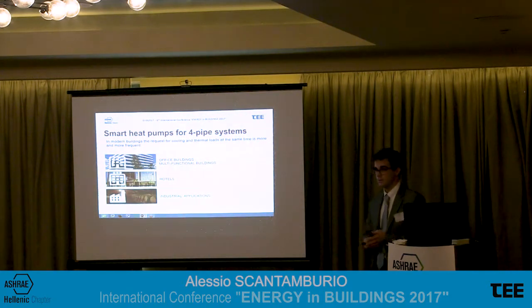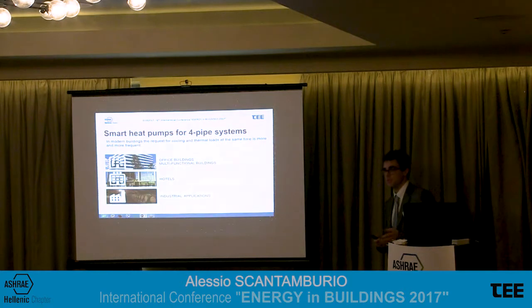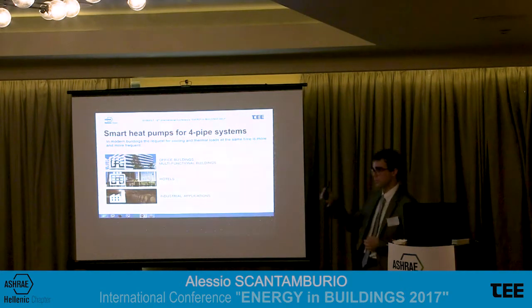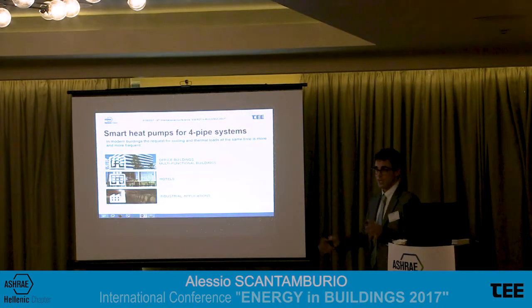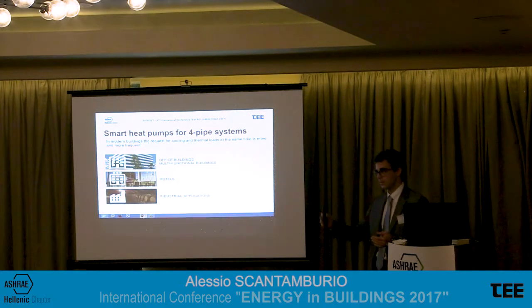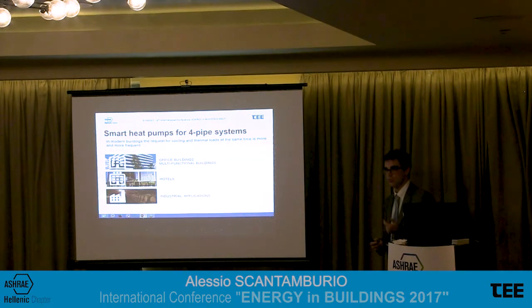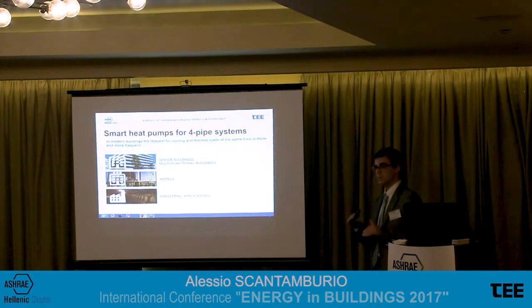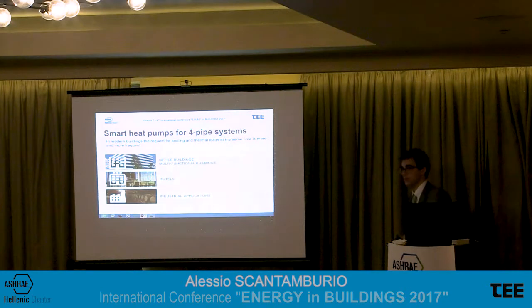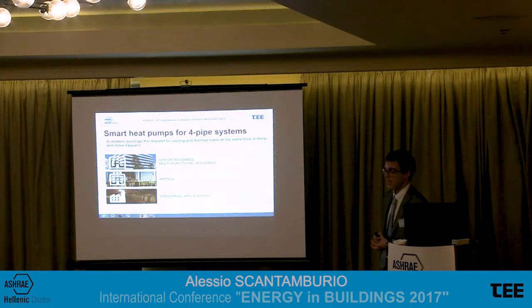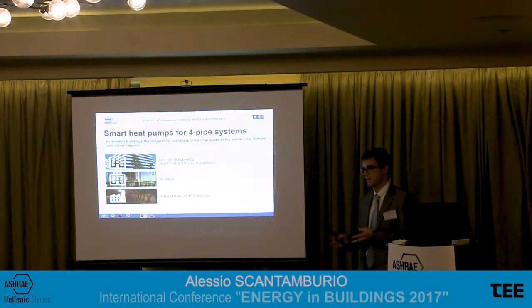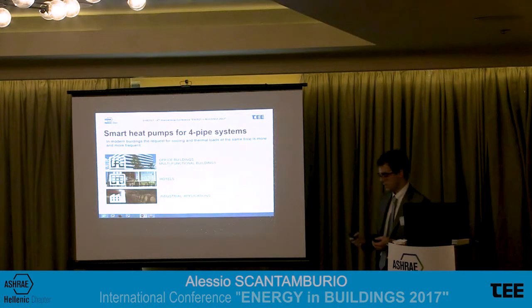Moving to hotels, especially large hotels in the middle season, we have some rooms facing north, while others face south. We have meeting rooms full of people, and other meeting rooms with solar heat gains due to a facade, for example. So it is frequent that in hotels I must supply hot water and cold water at the same time, with different combinations of load. For sure, in industrial applications there are many processes requiring heat in some part of the process and cooling in other parts, for example to cool down the machinery of the process. So it is common.